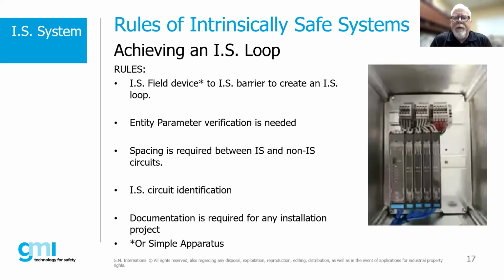But there are customers and end users who will say, no, I don't care, I want everything to be light blue. So that supersedes what's in the standards, either the NEC or the IEC standards. So it's always important, if I'm doing assembly work on behalf of a client, to understand their installation requirements for IS, because the standard gives you some leeway, but some customers may insist on more than what the standard requires.